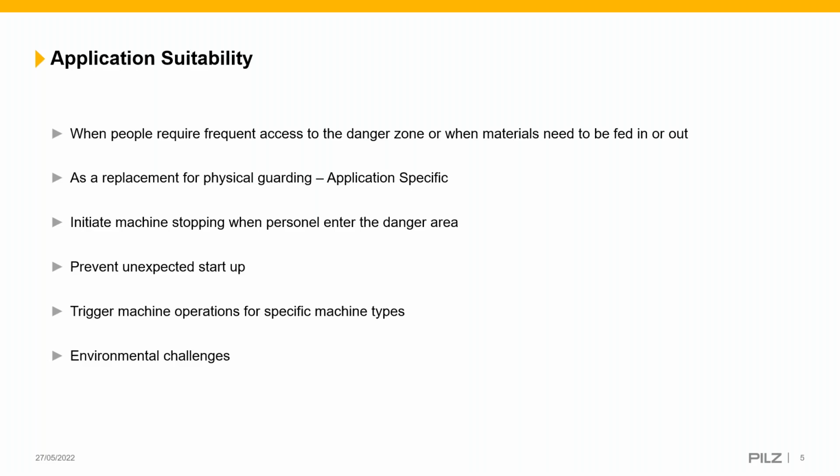So for instance, if you talk about presses, they have a single or double break functionality. So single break would be if the press is either automatically loaded or automatically unloaded, and you go in to load an item into the press, into the mold, you would break the light curtain, and as you come out and that light curtain remakes, it automatically cycles the press.